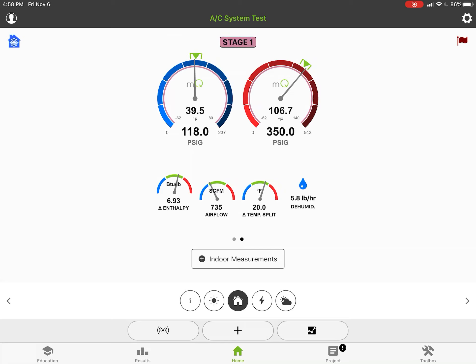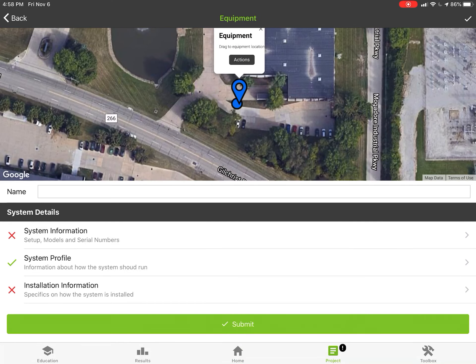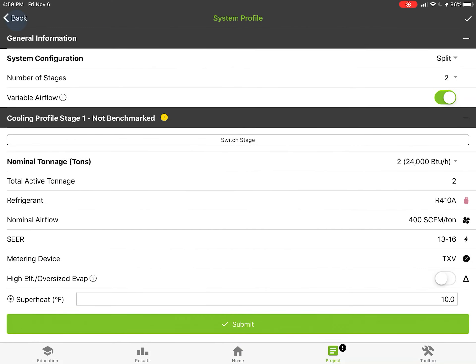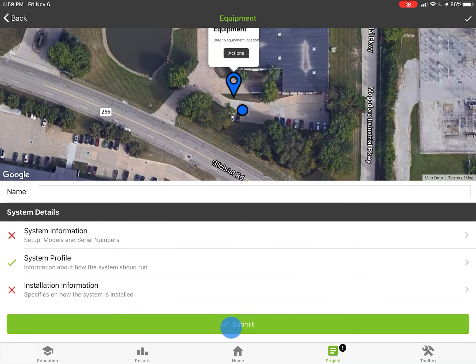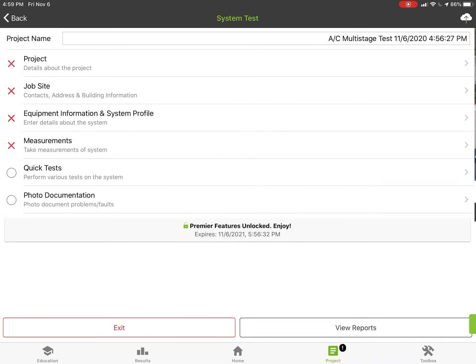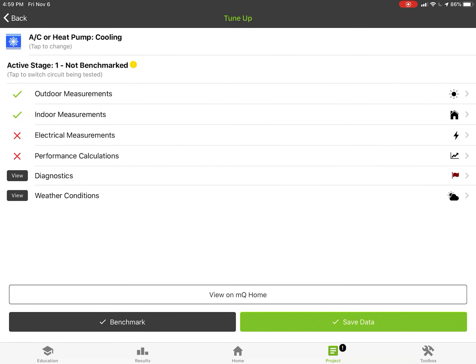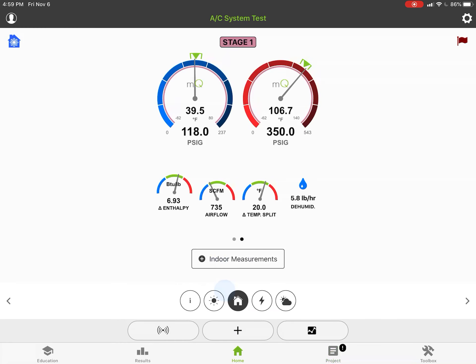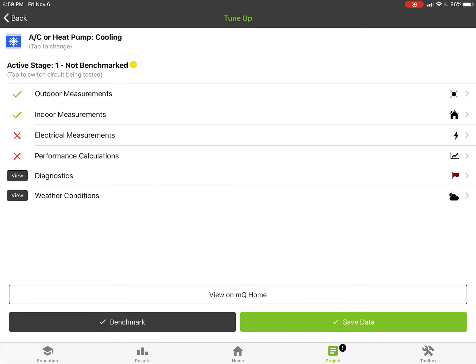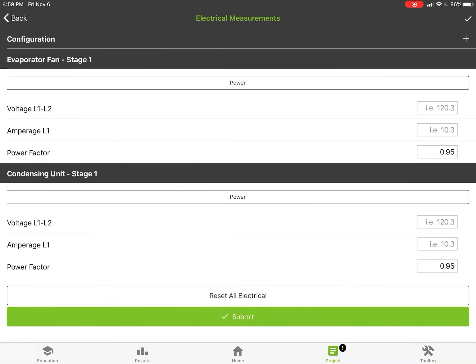That's based off the target temp split for this. This is doing a lot of stuff to swap between stages and get all of our electrical data and things like that. Let me go into the measurements section here. The measurement section now tells you what stage is active and whether or not it's benchmarked. We moved the benchmark button down here so it's a lot easier to work with. Then you've got a view home screen or you can go back in the project and save the data. It holds in your outdoor and indoor data on your probe, so if you move those around or switch the unit to second stage you don't have to move them.